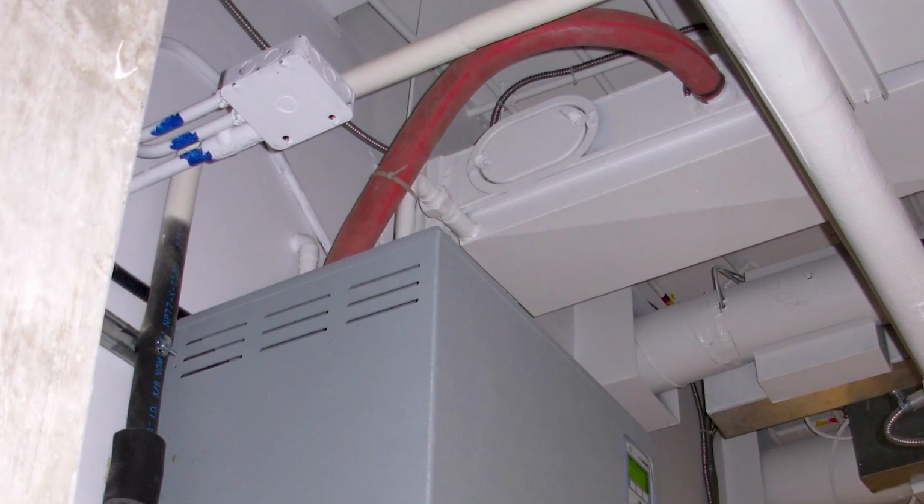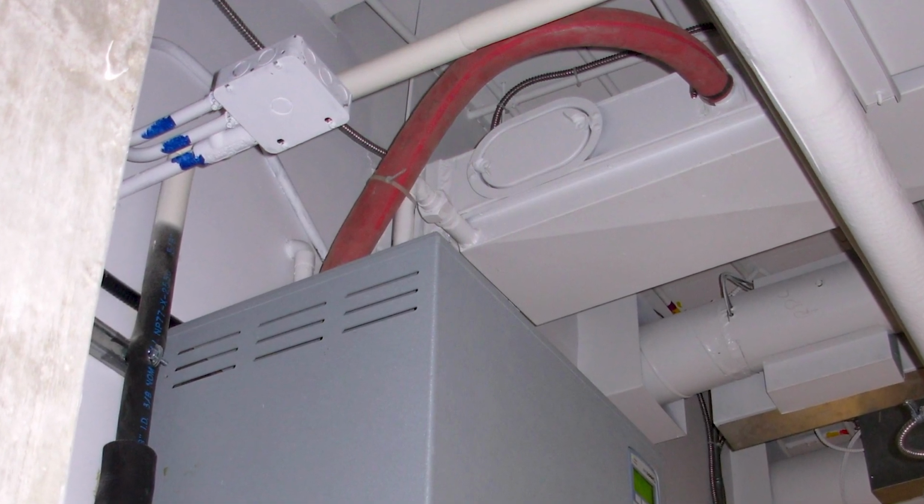I'm really glad that you touched on piping there, because I am curious, what are the materials that I should be using most when I'm thinking of the piping from my generator to my dispersion panel? It partially depends on capacity. If you're working with a small capacity system and it's nearby, a steam hose is great. It works perfectly. The problem is, if you get further away, how do you support it to make sure it doesn't sag? Then you're looking at hard pipe or tubing, typically stainless or copper, very common types of materials.